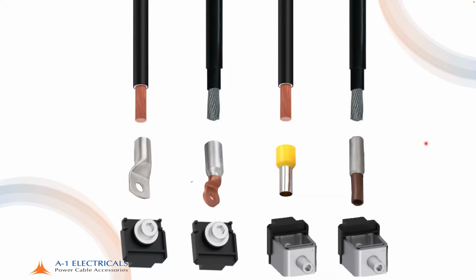Yeah, of course. There is no such thing that an aluminum conductor cannot be put on a copper bus bar. If you use a bimetallic lug like this lug and you correctly terminate it, it's not a problem. In fact, it's perfectly fine, Mr. Gandhi. Am I right? Yeah.